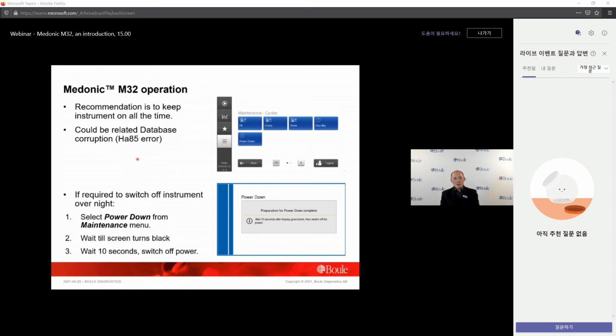By analyzing the technical files, we found some connection between the sudden power down of the instrument and the database corruption. So this is why we would like to bring up this topic, in case the end user shuts down the instrument often. The only correct way to power off the instrument is to go to the maintenance menu and use the power down button, and the instrument may give some warning message.